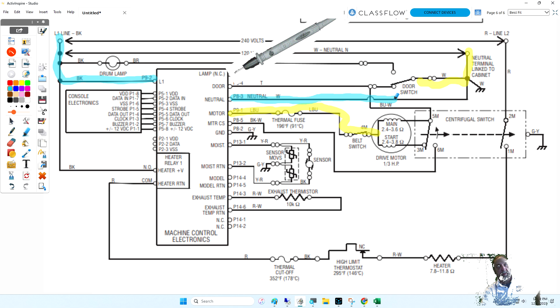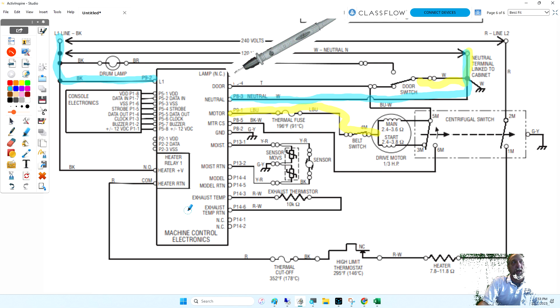Look at this. See this terminal right here? That's neutral for the board. These two terminals here is how the board gets power. That's what causes the board to light up. It doesn't go through the door switch. If it went through the door switch, every time you open and close the door, the clock would shut off or the computer would shut down.